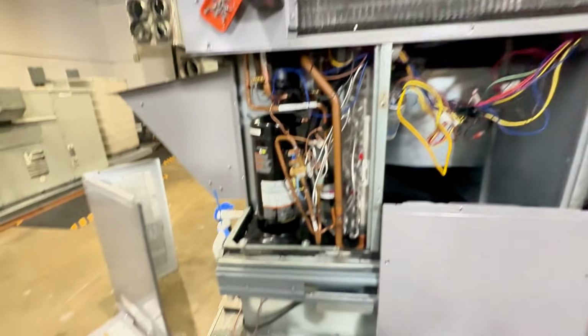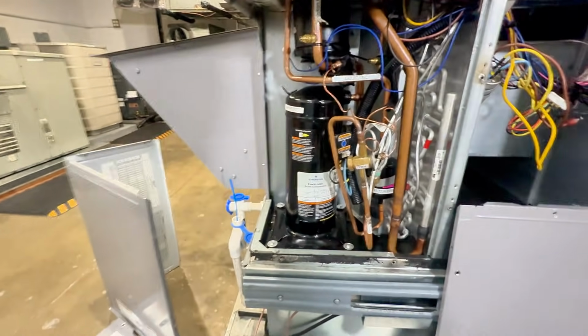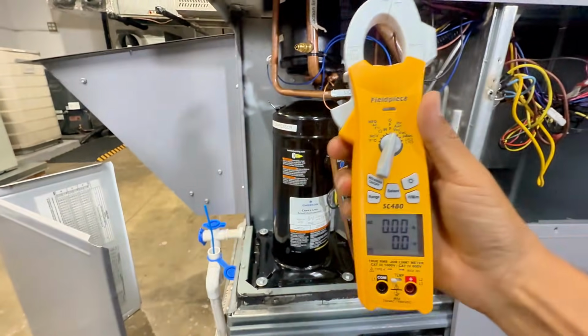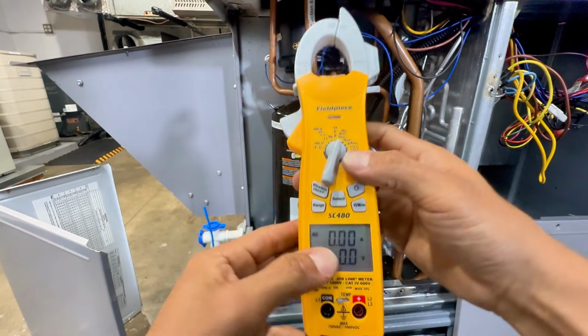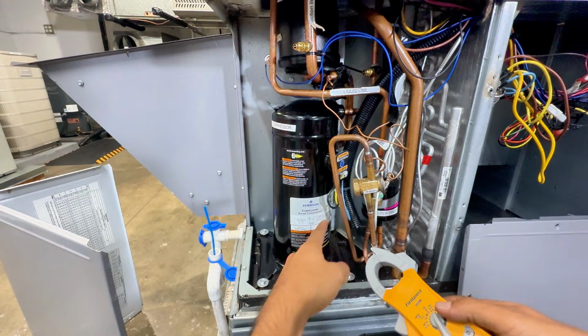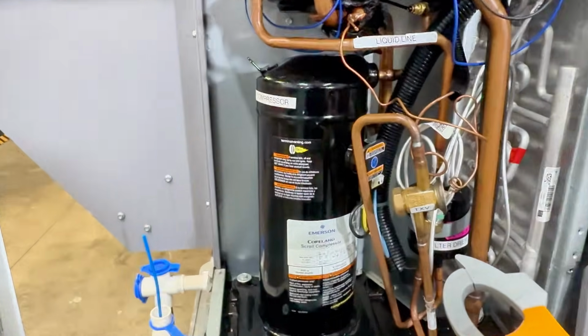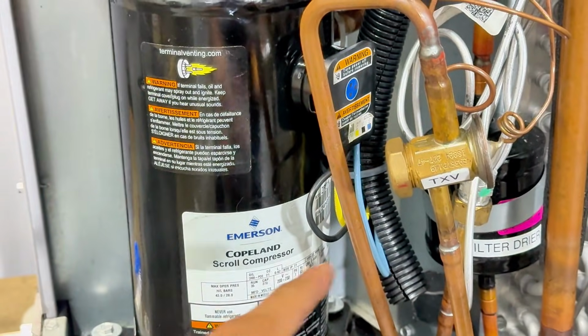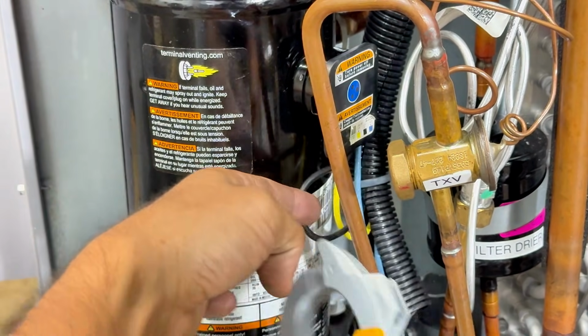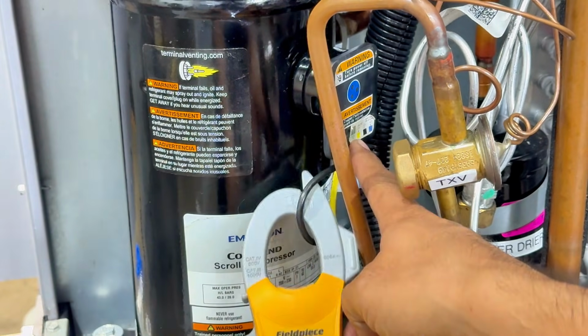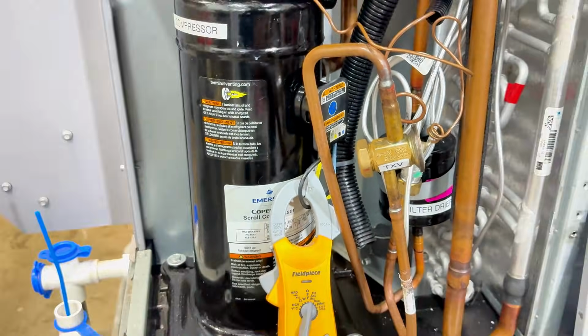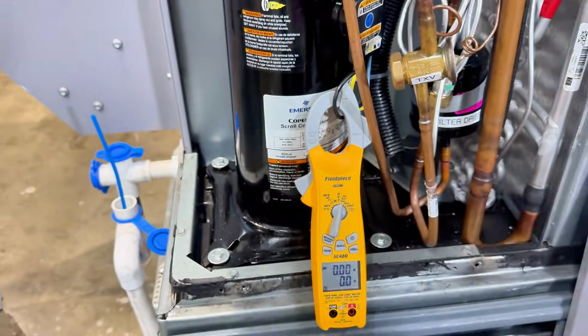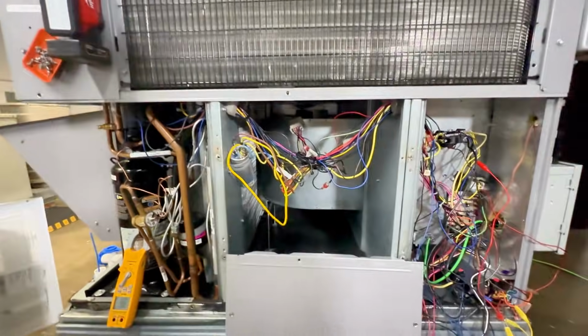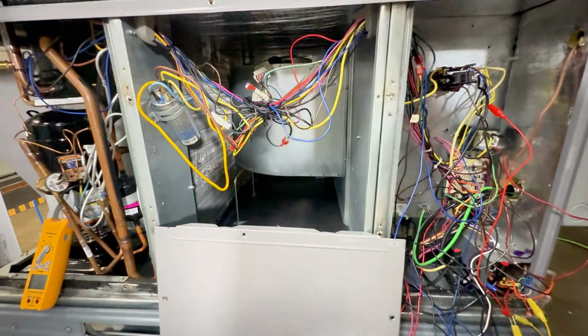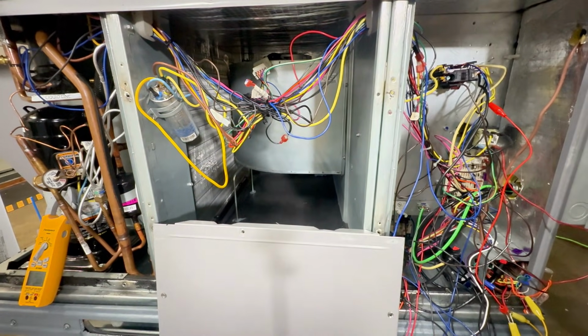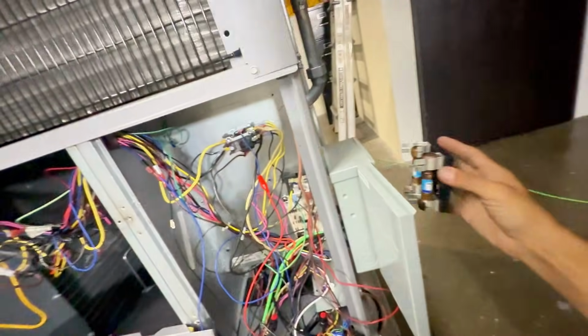So now I'm going to turn it on, but before that, we have our meter, we have to put it on amp draw, and we have to look for common. We've got blue, yellow, and black. Black is my common, and it also says it right here, black is common. Right now, obviously it's not on, you see, it's 0. So now let's go ahead and call for cooling. Let me go ahead and turn it on.